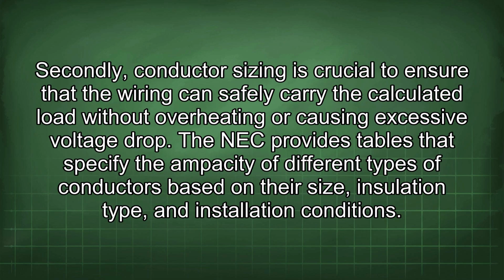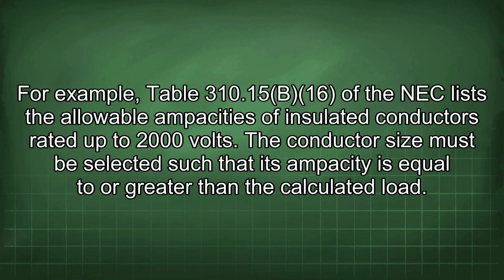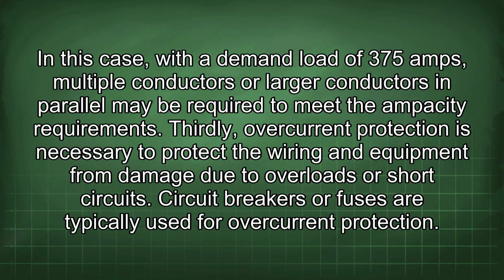Secondly, conductor sizing is crucial to ensure that the wiring can safely carry the calculated load without overheating or causing excessive voltage drop. The NEC provides tables that specify the ampacity of different types of conductors based on their size, insulation type, and installation conditions. For example, Table 310.15(B)(16) of the NEC lists the allowable ampacities of insulated conductors rated up to 2000 volts. The conductor size must be selected such that its ampacity is equal to or greater than the calculated load. In this case, with a demand load of 375 amps, multiple conductors or larger conductors in parallel may be required to meet the ampacity requirements.